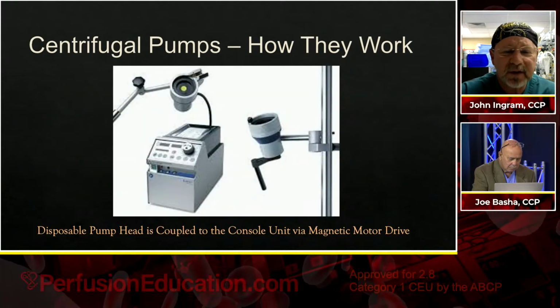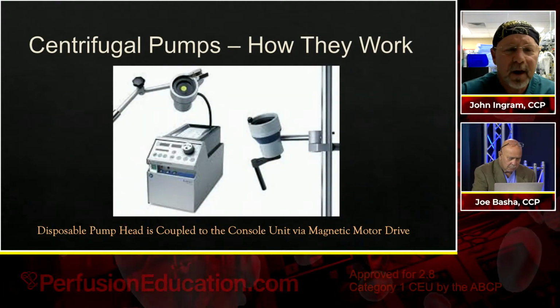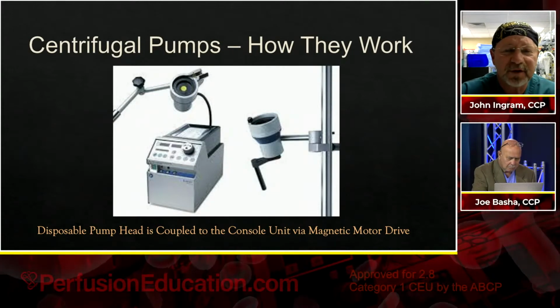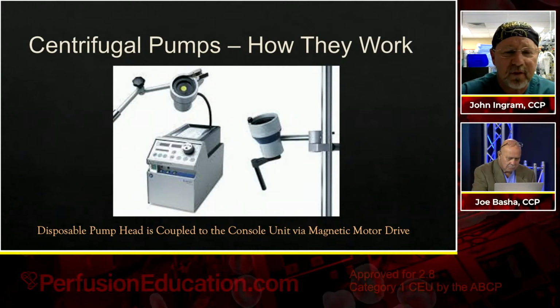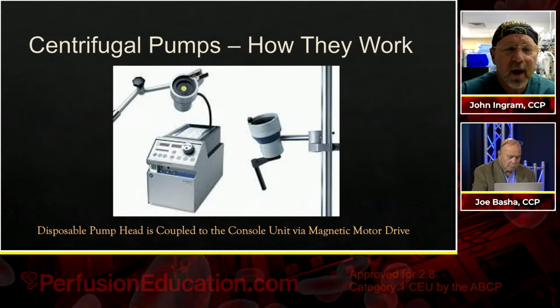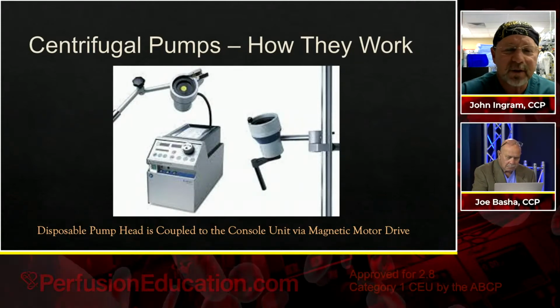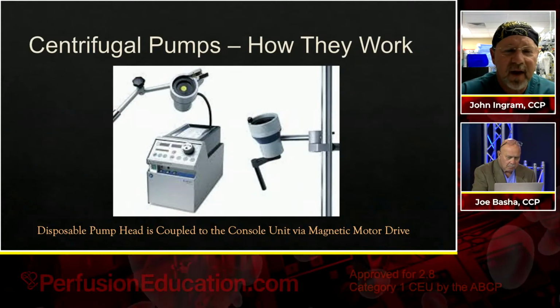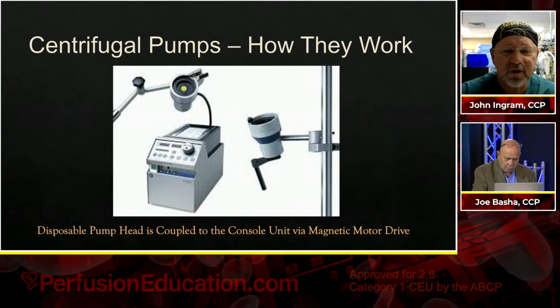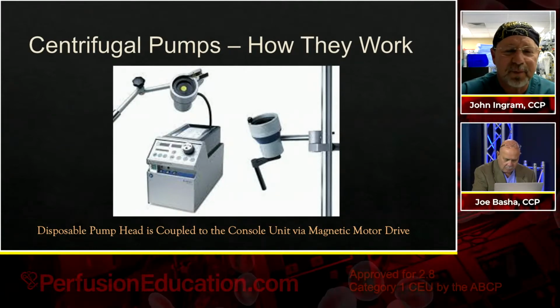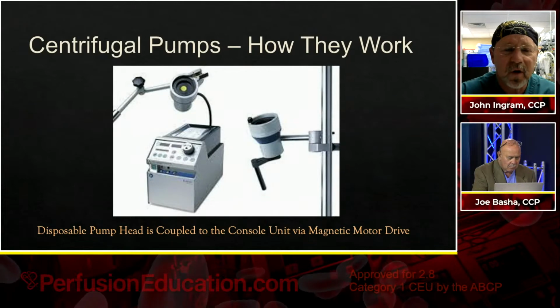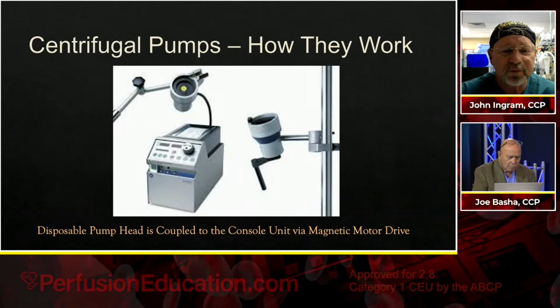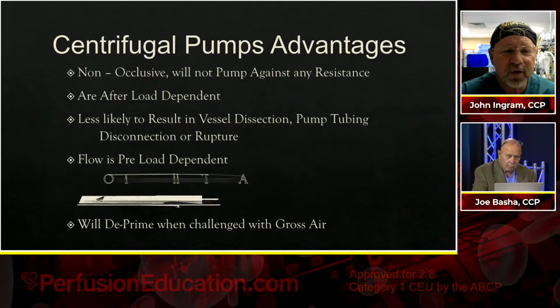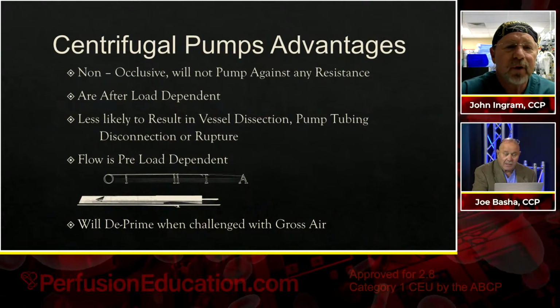So as I said about the magnetic coupling, these disposable pump heads you just saw need to go into some type of console unit. The disposable has a magnet on the base of it, and that couples magnetically with the console unit. The console unit then spins and causes also the disposable unit to spin at the same speed. But you can have decoupling as well, right? Yes. We're going to talk about that.